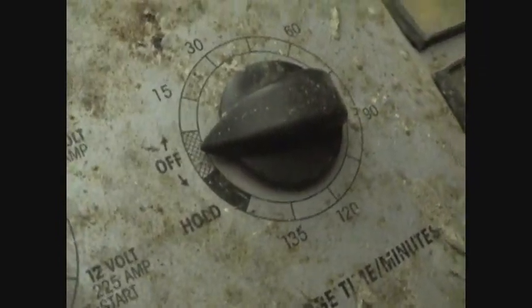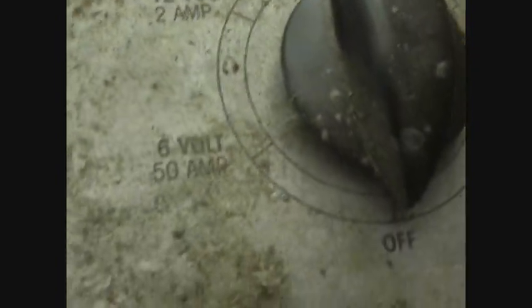Looks like the power hot lead comes into this switch here, which is the timer apparently, and then comes on down in here and goes to this first lead of the transformer. It looks like all the various voltage and current selections you have available are controlled by various taps on the primary side of the transformer.